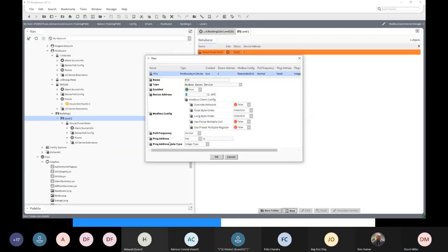So when you nominate an address in Modbus, you can nominate it as a hexadecimal number starting at 0, or as a decimal number, again starting at 0, or you can use the Modbus convention, which is something like 40001.